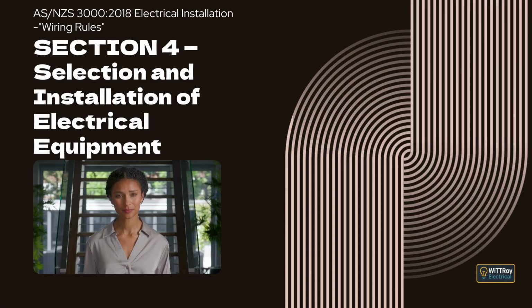Clause 4.5.2.1 General. This clause explains that lamps, luminaires, and their associated auxiliary equipment must be installed so they do not cause excessive temperature rise, ignition, or deterioration of materials they are mounted on or materials they illuminate. It explains that luminaires must be suitable for the highest temperatures they are likely to experience from external influences and must be installed in accordance with the manufacturer's instructions, taking into account the highest rated lamp that may be used.